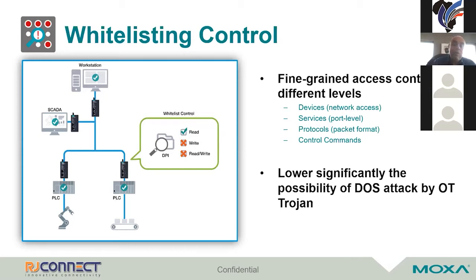So if you do have a denial of service trying to attack and write to multiple devices, it will prevent that if you're only allowing read and you're not allowing write, or if you're only allowing certain information to read and only certain information to write, or certain commands can be written and the rest can only be read.